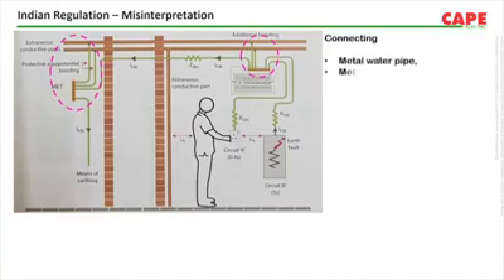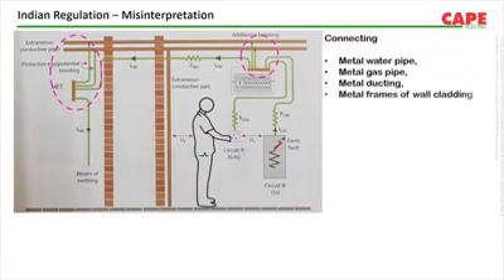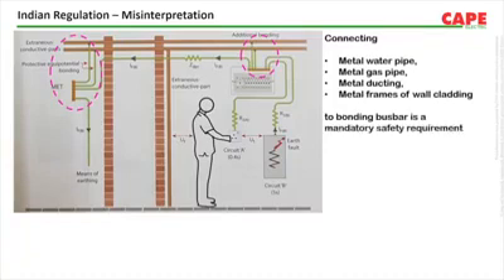Now in the picture you can see that at two places these are connected together. This connection is to reduce the fault voltage or touch voltage which can be experienced between two simultaneously accessible metal parts. This is a mandatory electrical safety requirement. An electrical engineer need not be explained to follow the safety measure. Every electrical engineer is supposed to know and understand the need for this protective provision called protective equipotential bonding.